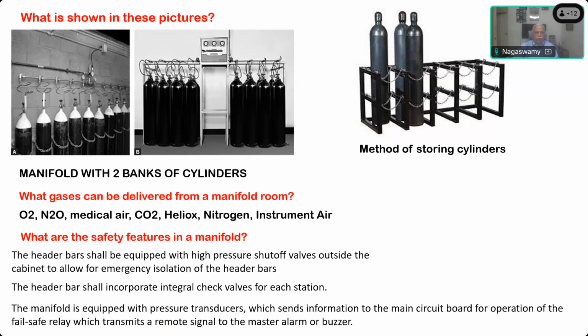Whenever one bank gets empty, the pressure transducer will sense the fall in pressure and immediately send an alarm, even though the other bank automatically opens and starts supplying without any interruption. But to indicate that this bank has become empty, there will be an alarm, so that the person guarding the manifold room will know that these cylinders have become empty and will start replacing them with fresh ones. So that alarm or buzzer will sound once all the cylinders of one bank become empty.